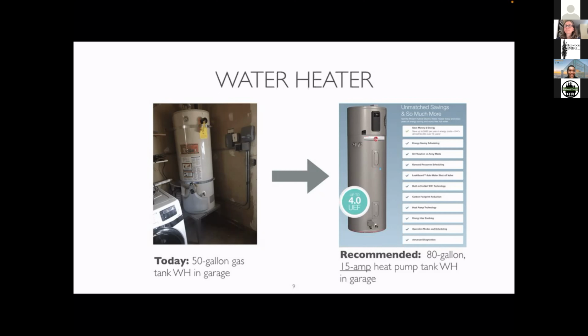On the left is the existing 50-gallon gas tank water heater, located in the garage - a perfect situation for replacing with a heat pump water heater. You need 700 cubic feet of space around a unitary heat pump water heater, like the one on the right, for it to have space to collect heat and put it into the tank. The one on the right is a Rheem 80-gallon, 15-amp heat pump water heater, going in the exact same place with a very similar form factor. When moving from gas to electric heat pump, we recommend upsizing the tank because the recovery time is slower for a heat pump.